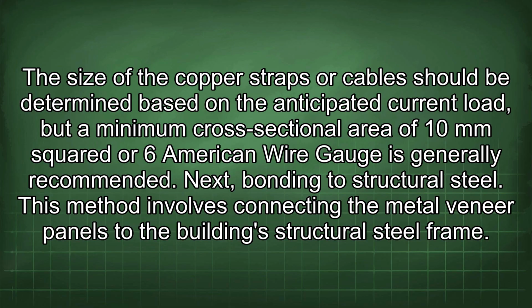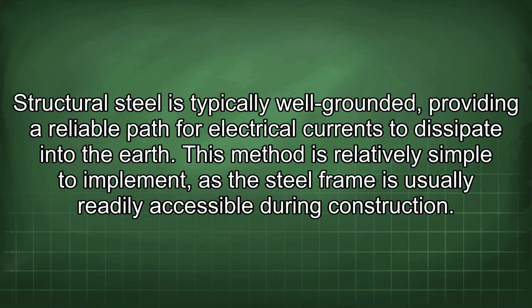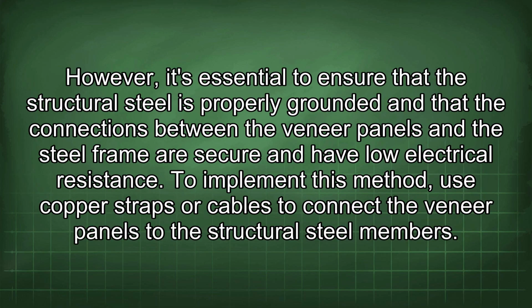Next, bonding to structural steel. This method involves connecting the metal veneer panels to the building's structural steel frame. Structural steel is typically well grounded, providing a reliable path for electrical currents to dissipate into the earth. This method is relatively simple to implement, as the steel frame is usually readily accessible during construction. However, it's essential to ensure that the structural steel is properly grounded and that the connections between the veneer panels and the steel frame are secure and have low electrical resistance.